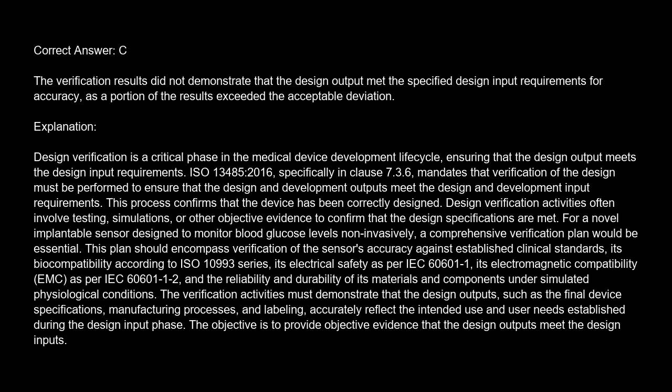The correct answer is C. The verification results did not demonstrate that the design output met the specified design input requirements for accuracy, as a portion of the results exceeded the acceptable deviation. Explanation.